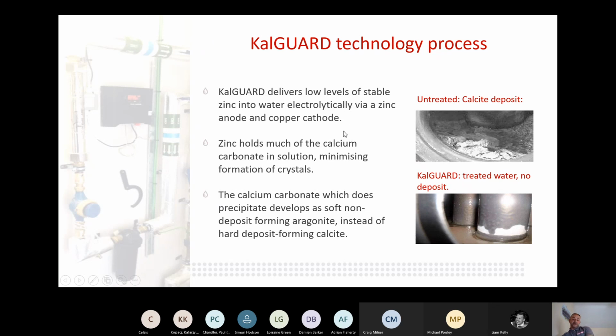What zinc does is hold most of the calcium carbonate in solution, changing it from calcite into aragonite. I always refer to this as Lego bricks or stickle bricks that stick together and accumulate on the sides of pipes and other equipment as scale. By adding zinc and changing it to aragonite, it becomes a soft, flake-like structure that can't stick to anything or sit on top of each other. It's fragile and will wash away in the water flow.